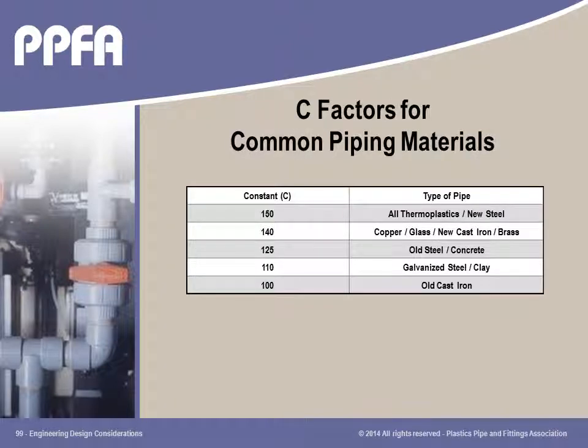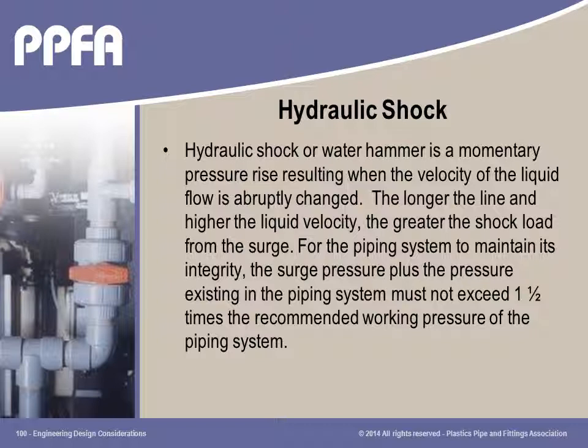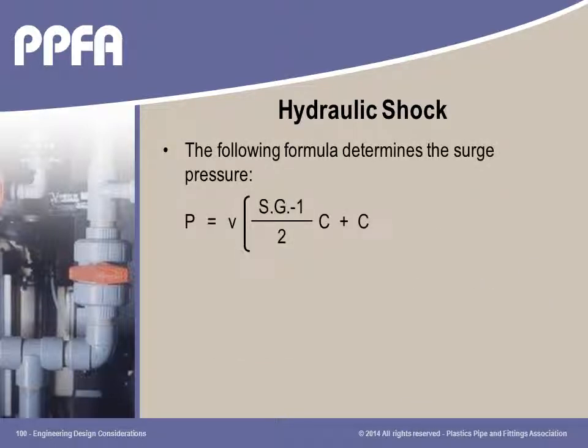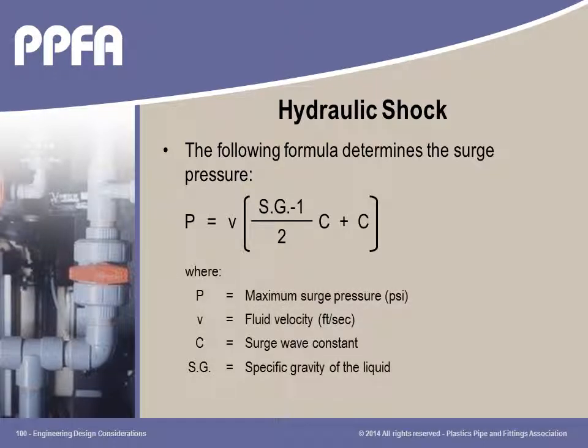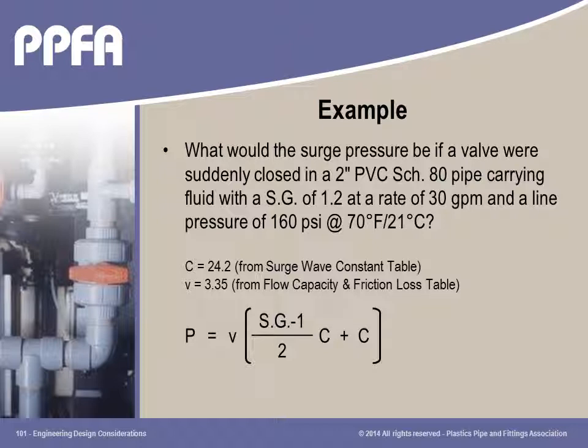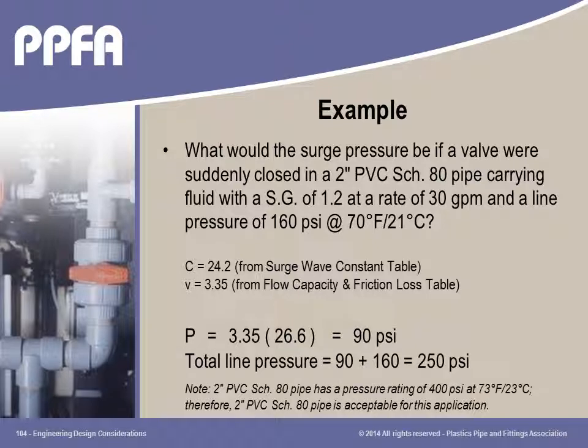Common thermoplastic piping materials have a friction loss coefficient, or C factor, of 150. This factor for thermoplastics is higher than most other piping systems and normally maintains its value throughout its use. The end result is there is less friction loss in thermoplastic piping compared to most other piping systems. With proper design, the engineer can minimize the effect of hydraulic surge or water hammer. However, it is prudent to calculate this possible event, especially if the fluid velocity is higher than 5 feet per second and there are pumps, valves, and long runs of pipe. To determine if the pipe working pressure is capable of handling the surge, we must add the surge pressure to the line pressure. In this example, the total pressure of 250 psi is well under the maximum working pressure for this piping application.